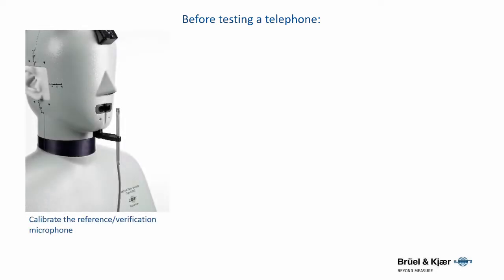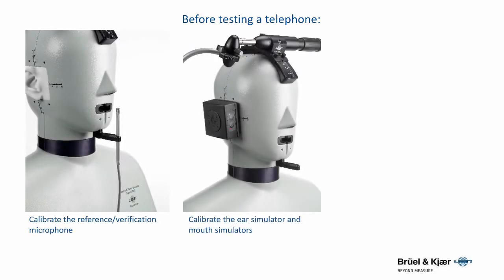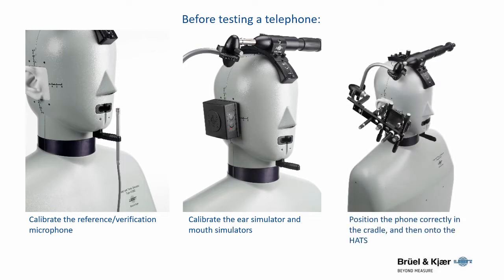Before testing a telephone, calibrate the reference verification microphone, calibrate the ear simulator and mouth simulators, position the phone correctly in the cradle, and then onto the HATS.